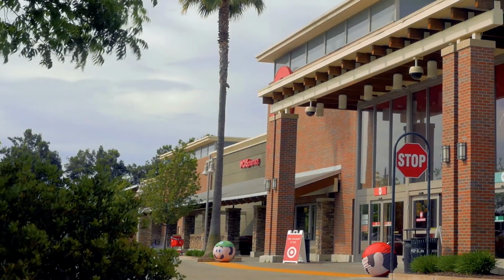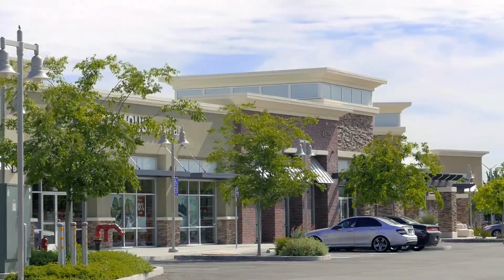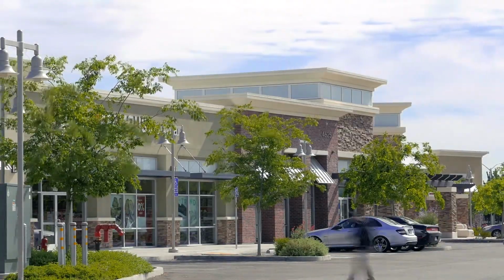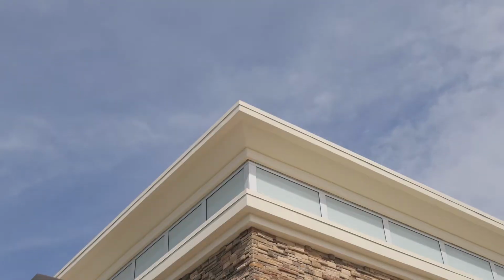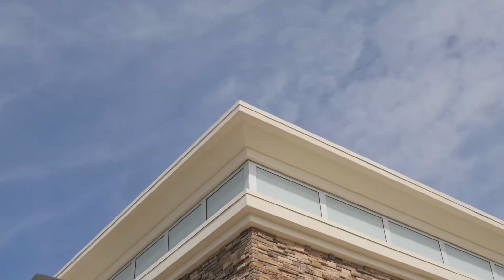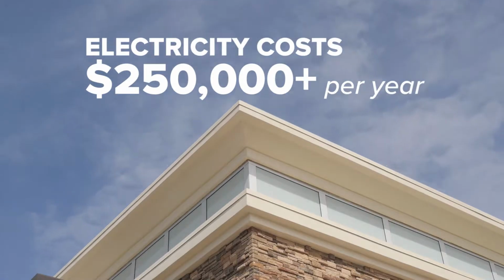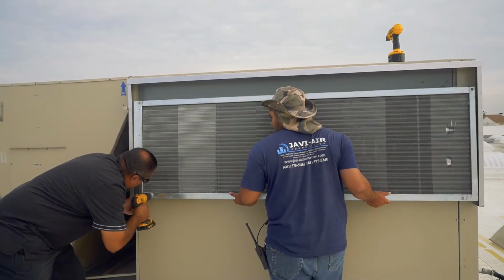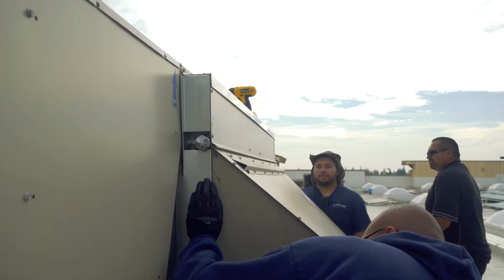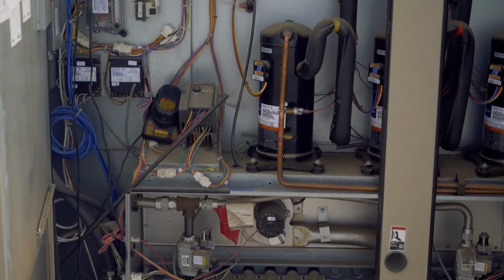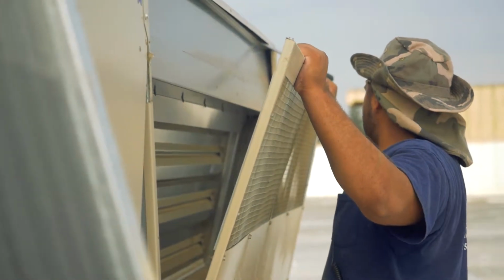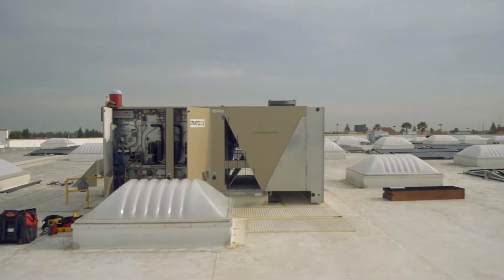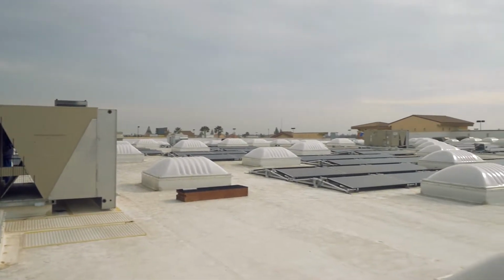The average annual cost of electricity used in retail buildings in the United States is $1.21 per square foot. For a box retail store, electricity costs can exceed $250,000 per year. In many climates, air conditioning accounts for 25 to 50% of these costs, largely because the need for cooling coincides with peak electrical demand, when electricity costs may be at a premium.